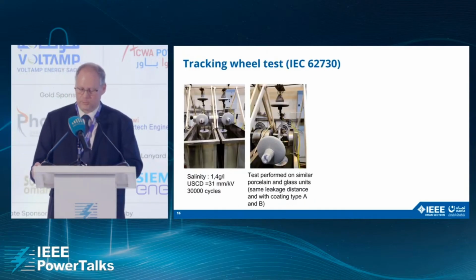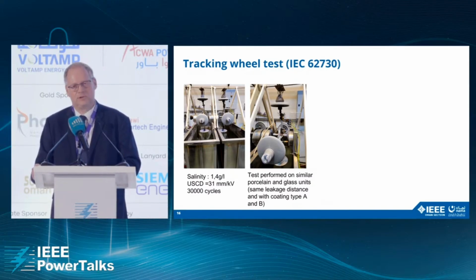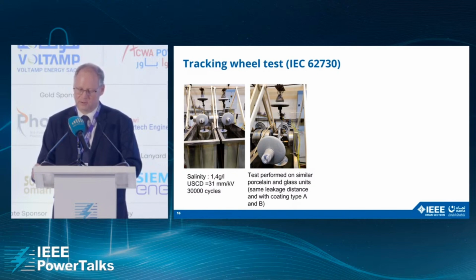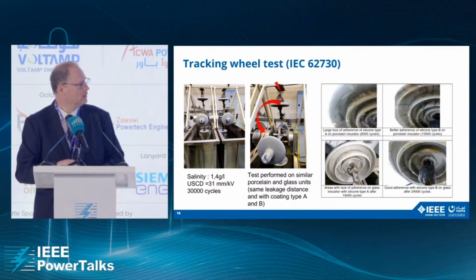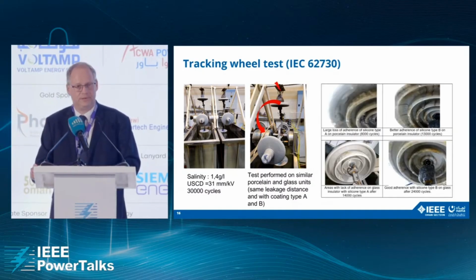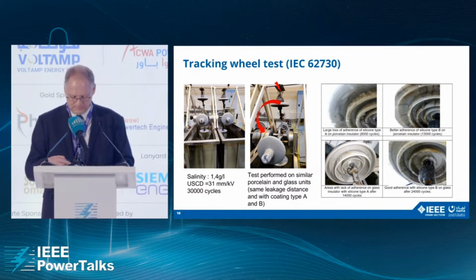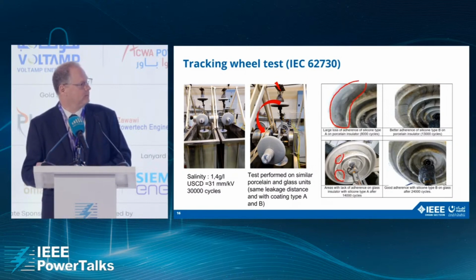So an interesting test to reproduce this phenomenon on coated insulators is the tracking and erosion wheel test defined in the IEC 62730. This test has been used for polymer insulators with the aim of defining the ability of housing material to sustain strong regular dry band arcing. But it can be used as well for coated glass or porcelain insulators. Here are some examples of tests performed for investigation purposes on either porcelain or glass insulators with the same features and with two different coating chemistries, noted A and B. You can see that on the left, coating A exhibits loss of adherence after the test, whereas coating B does not show any damage.